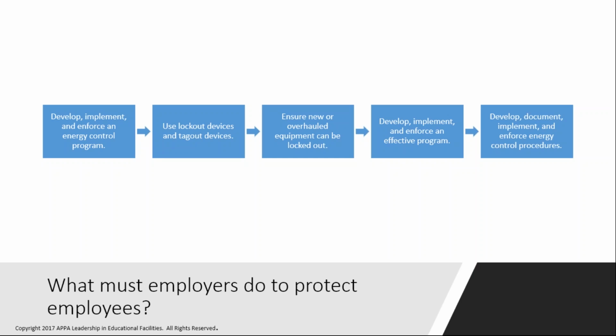Ensure that new or overhauled equipment is capable of being locked out. This means major capital renewal projects should have lockout capabilities included in the design and/or replacement work. While design engineers should know about this requirement, if you decide to do your own capital renewal or major maintenance project, you must be aware of the requirement too.